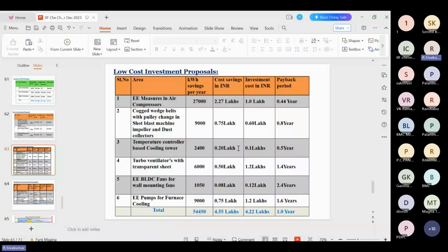And the turbo ventilator with the transparent sheet in the rooftop. The rooftop is fully covered with sheets, and even in the daytime they are using many lights. Almost 80 to 90% of the installed lights are used for 24 hours. If a turbo ventilator with a transparent sheet is there, natural light enters the foundry, and the hot air is also evacuated from the foundry process. So they can save 6,000 units, with 1.2 lakhs investment and 0.5 lakhs saving. Almost 1.4 years is the payback period.